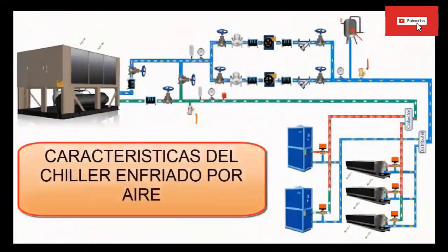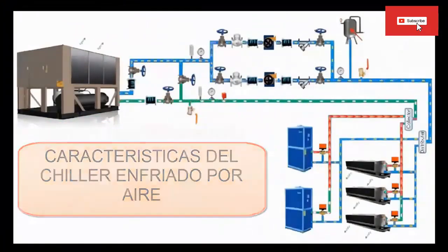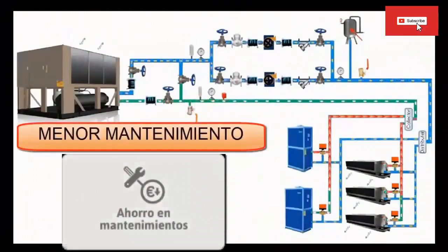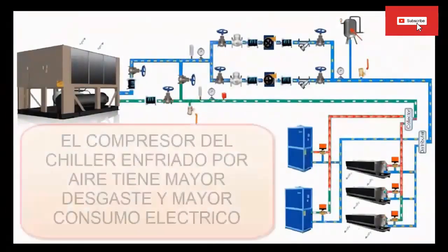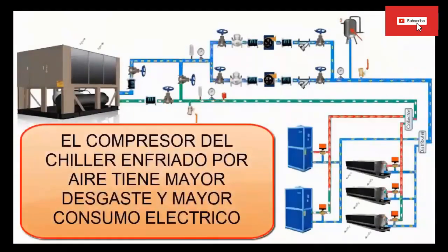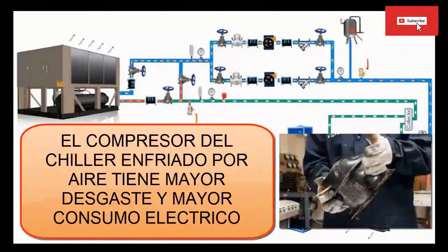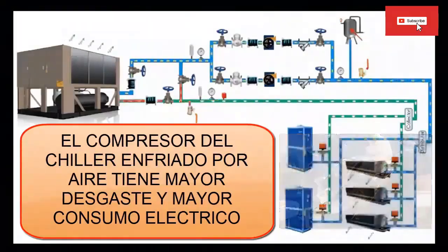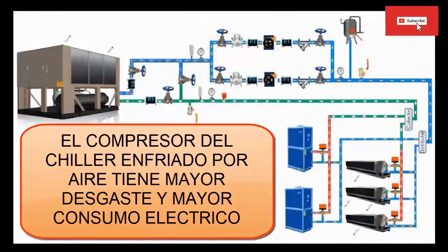The air-cooled condenser chiller is very attractive, especially when the customer does not have a fixed maintenance department, because the supervision of this equipment is minimal. Remember that the chiller compressor must send the refrigerant to the condenser. Therefore, if the latter is colder and at lower pressure, it will be easier to introduce the refrigerant and start condensation. This is the main reason why water-cooled chillers are more efficient than air-cooled ones.